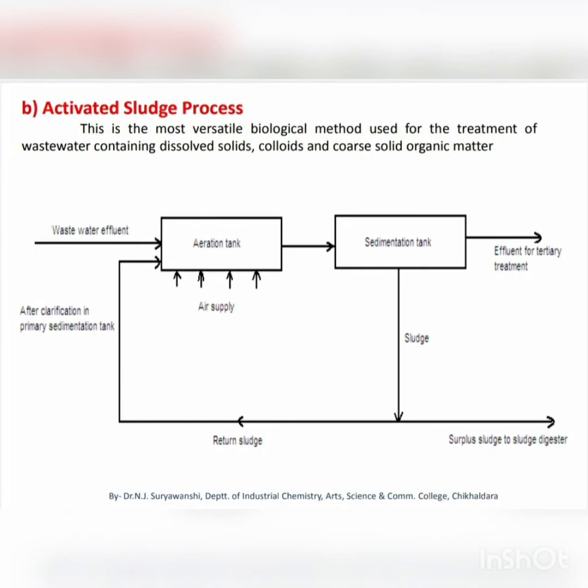The microbial flocs formed in this process contain zooglial masses of living organisms along with their food and slime material, that is, an unpleasantly thick and slippery liquid substance, and act as active centers for biological oxidation, and that is why it is called activated sludge. For this method, at least 0.5 ppm oxygen must be present. Oxygen is provided either by mechanical or by diffused aeration systems.